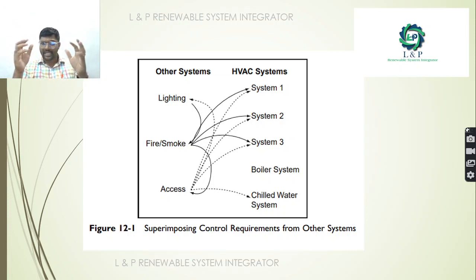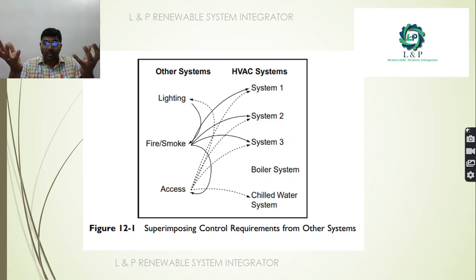lighting control system and access control system are normally integrated. Okay, if there occurs any sort of issues, the light should come on. And also, if there occurs any sort of fire, the heating, ventilation and air conditioning system should get shut down. Okay, if there occurs any sort of access control issues, or if there occurs any sort of fire alarm issues, then the access control system should open. Like this, these are all interlinked systems. Even the chilled water system has an interlock with the access control system. Okay, and most importantly, even with the fire alarm systems also, it has interlocks.